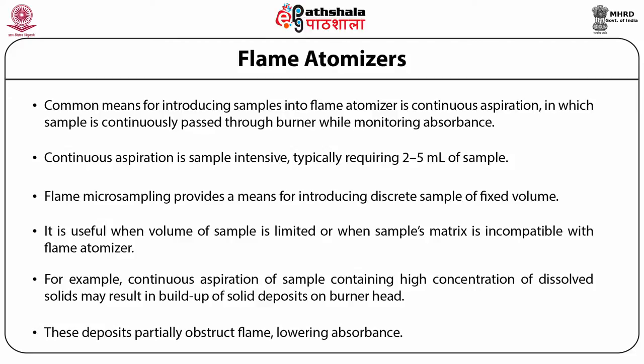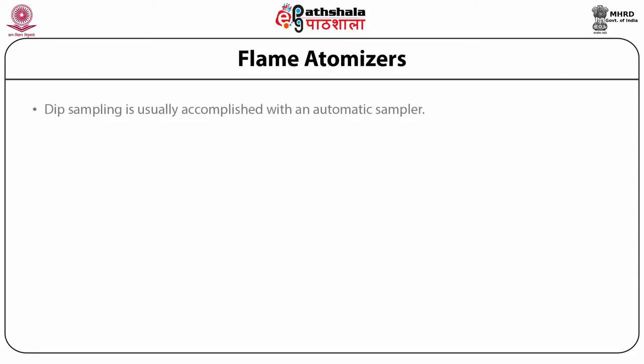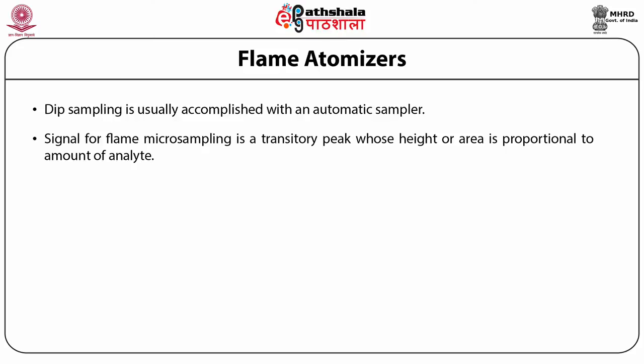These deposits partially obstruct the flame, lowering the absorbance. Flame microsampling is accomplished using a micropipette to place 50 to 250 µL of sample in a Teflon funnel connected to the nebulizer, or by dipping the nebulizer tubing into the sample for a short time. Dip sampling is usually accomplished with an automatic sampler. The signal for flame microsampling is a transitory peak whose height or area is proportional to the amount of analyte injected.